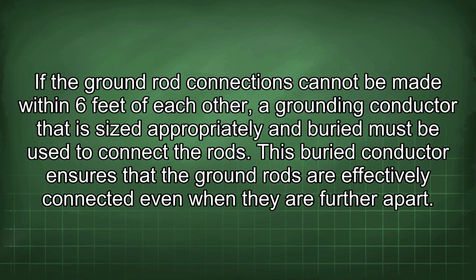If the ground rod connections cannot be made within 6 feet of each other, a grounding conductor that is sized appropriately and buried must be used to connect the rods. This buried conductor ensures that the ground rods are effectively connected even when they are further apart.